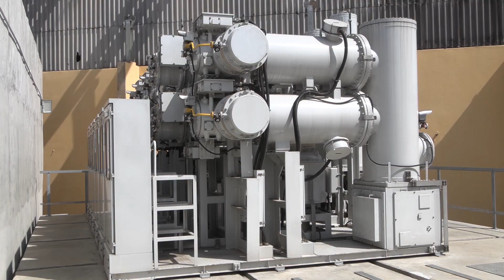We just energized the new upgraded station, the GIS 132 and 33 kV, and then 3 by 60 MVA transformers, T1, T2, and T3. This is our Apapa Road 132 kV to 33 kV transmission station. With the addition of 2 transformers, the bulk electricity transmission capacity of Apapa substation has increased from 60 MVA to 180 MVA. The station was 60 MVA, but today we have an additional 2 of 60 MVA, making it 3 by 60 MVA.